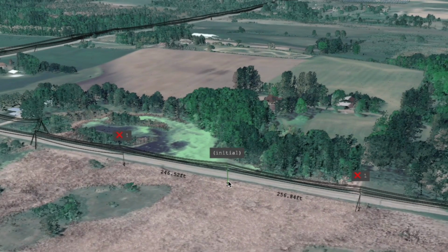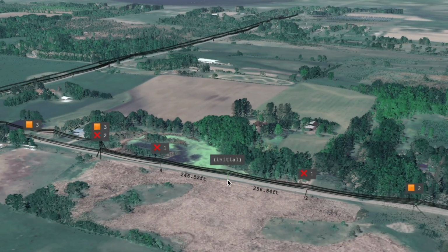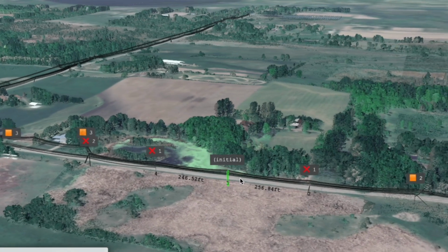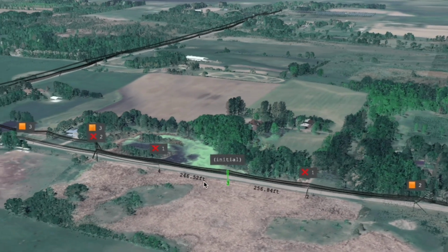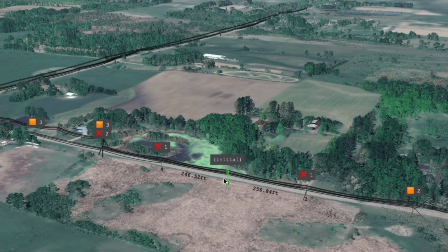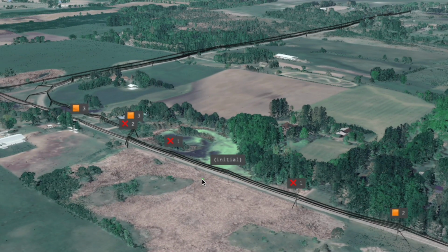Neara is now calculating how forces are being redistributed across all of the connected structures, so we can determine which can withstand the increased tension and which will also fail. In this scenario, we're seeing 3 additional poles fail, 1 on the right and 2 on the left side of the original pole. You can also see that the poles on either side of the cascade are now approaching critical load. This shows how failure ripples across the network, across multiple spans.